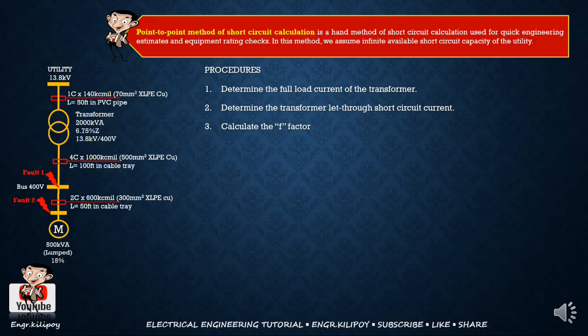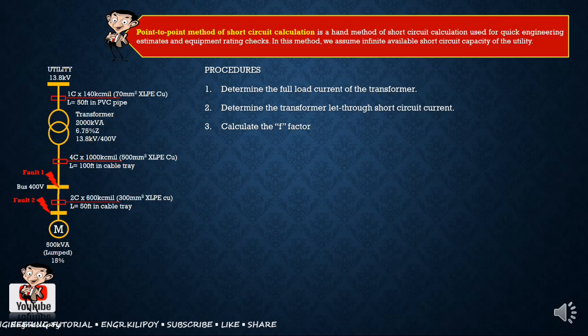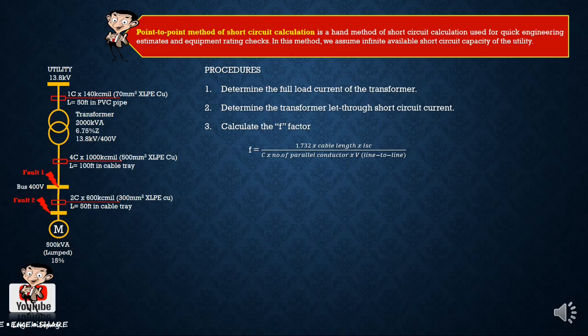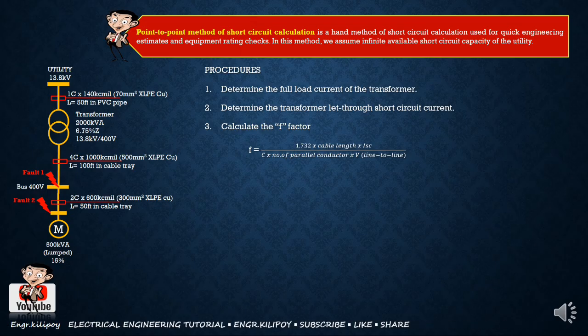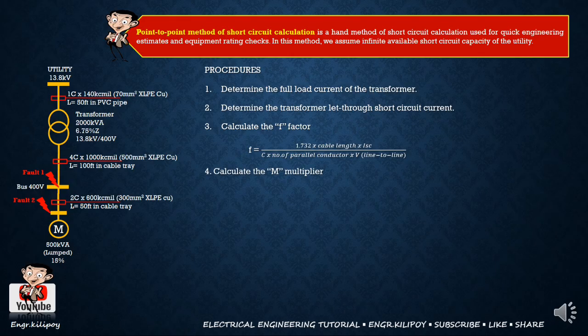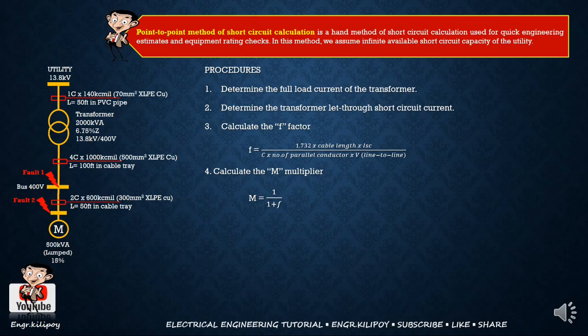So in this method, kailangan mong i-calculate yung tinatawag na F factor. So ito yung formula ng F factor. So this is square root of 3 for 3 phase. And you need the cable length and the available short circuit at that point. C factor, kailangan natin yan. Cable C factor, i-discuss natin yan mamaya. And kailangan mo rin ma-determine yung number of parallel conductor per phase ng ating system and yung ating line-to-line voltage. After calculating the F factor, kailangan natin i-calculate yung M multiplier. So it's simply this one, 1 over 1 plus the F factor. So yun yung ating multiplier.